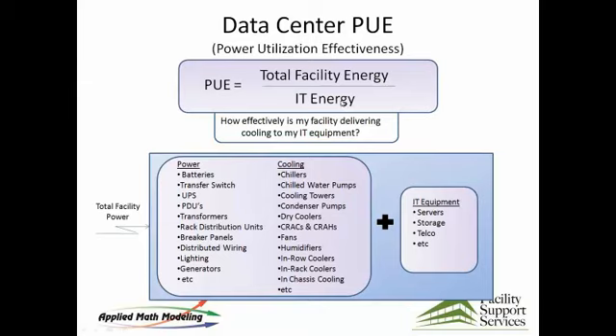The way to do this most effectively for those who are trying to build models is, if it's an existing data center, go into your data center and take a probe and measure the supply temp coming out of the CRAC, and then use that as a boundary condition in the model. Once you set these, you can then run the model and look at these, see what the model predicts on output, and if they match within 10%, then you're home free. You've at least captured the physics in the room. It's a very quick way to validate your model.